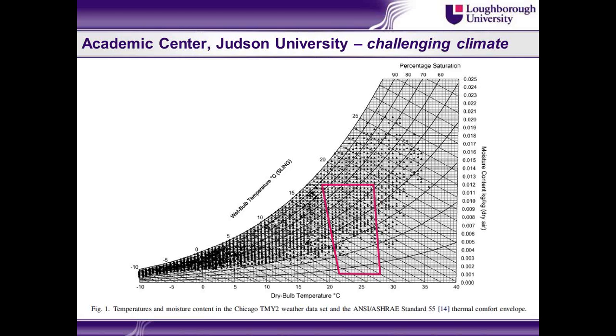So looking at this climatic data for Chicago, we can see that there's some hours up here whereby it's impossible to get into the comfort envelope without providing some mechanical cooling and dehumidification. Similarly, in the middle of winter in Chicago, when the air comes in from the east, the air down here is so skin-crackingly dry that if we were to heat it up, it would be so dry we'd have problems with dry lips, dry eyes, and the rest of it. So there's humidification and heating needed down here, and there's dehumidification and cooling needed up here. But there's a whole raft of hours where a passive solution is likely to work. So all of these hours here, we simply move these to the right by introducing them into the building. They'll pick up some of the heat inside the building, and then they'll move into the comfort envelope. So that's the strategy that we've got for this building.